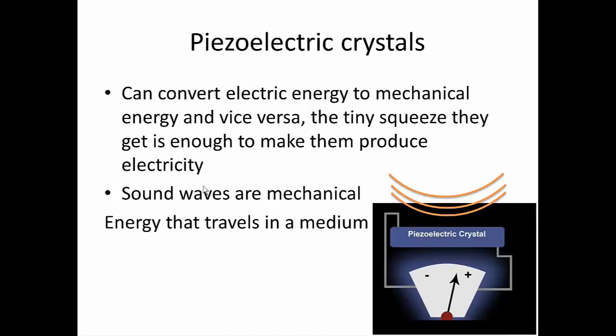Let me say a couple of things about the piezoelectric effect. Piezoelectric crystals, as they used to be used in ultrasound devices — now changed to a slightly different material — have the property that they can convert electric energy into mechanical energy and vice versa. So if you squeeze them, they will produce electricity. If there is an incoming sound wave that squeezes the crystal, the needle on the voltmeter will actually move and you create a current. On the other hand, if you apply pulsed electricity to them, you will create sound waves. These are called direct and indirect piezoelectric effects.